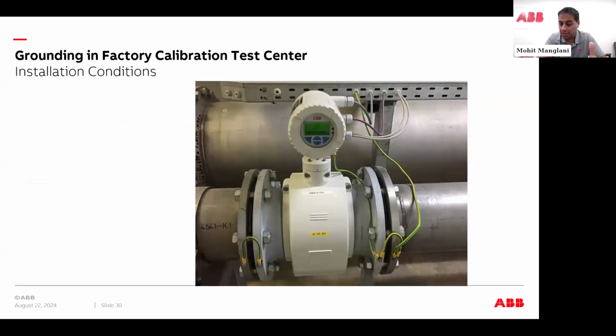Just so you can see what we do and how we test it on the rig. So obviously, when ABB or when any manufacturer builds a mag meter, we test it in lab conditions. We're inside of a clean area, we have clean water, perfect process. When we make mag meters, we give you an accuracy based on ideal conditions. Obviously, in the field, you're far from ideal. It might be power supply, it might be cross bonding, it might be other electrical disturbances. The idea is that you want to make sure the installation at which we test and calibrate matches it as close as possible to the field.